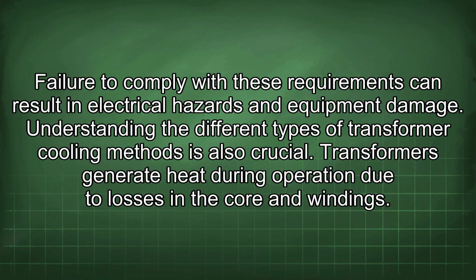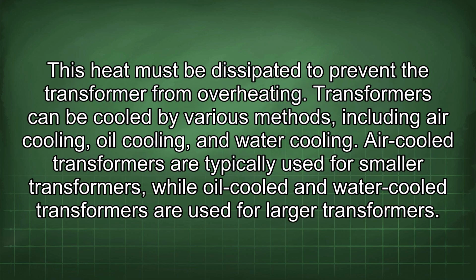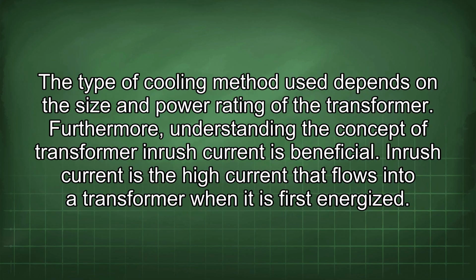Understanding the different types of transformer cooling methods is also crucial. Transformers generate heat during operation due to losses in the core and windings. This heat must be dissipated to prevent the transformer from overheating. Transformers can be cooled by various methods, including air cooling, oil cooling, and water cooling. Air-cooled transformers are typically used for smaller transformers, while oil-cooled and water-cooled transformers are used for larger transformers. The type of cooling method used depends on the size and power rating of the transformer.